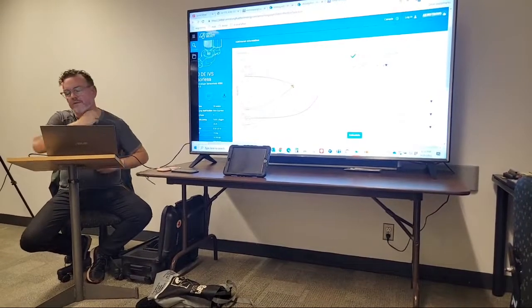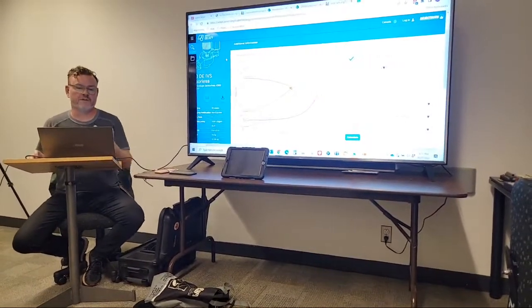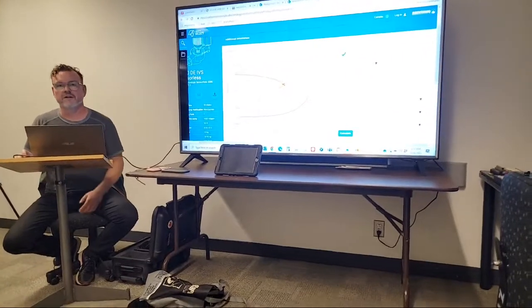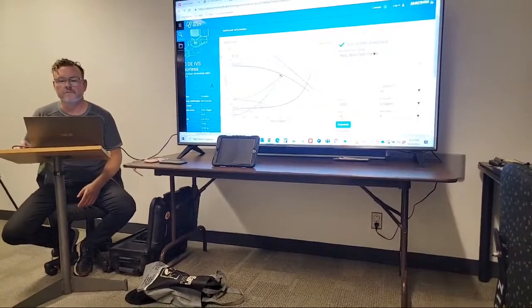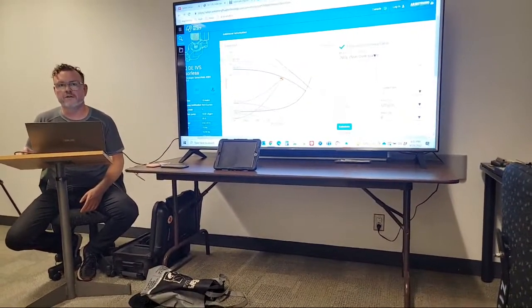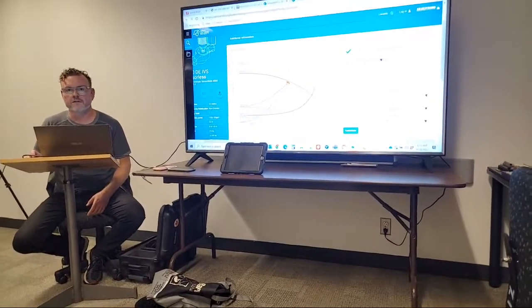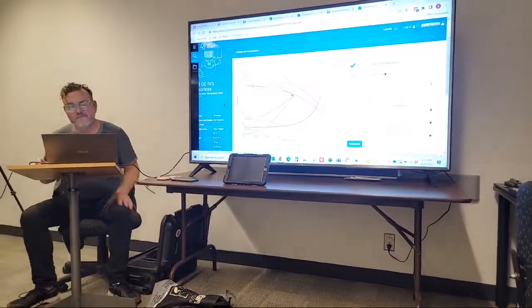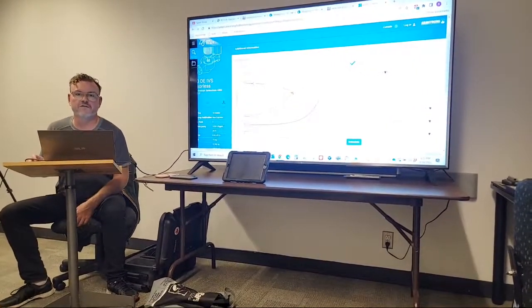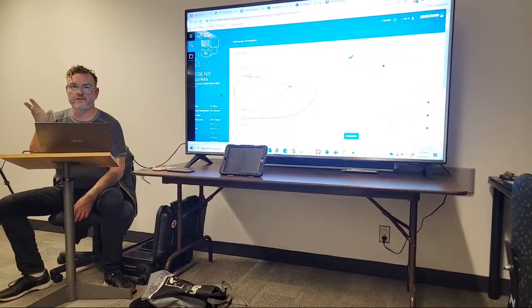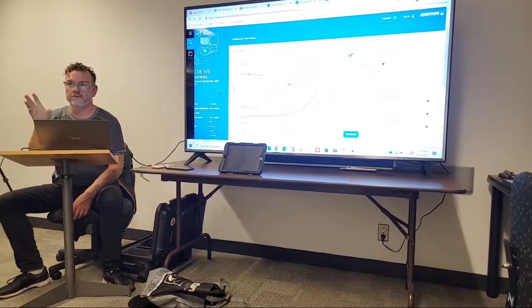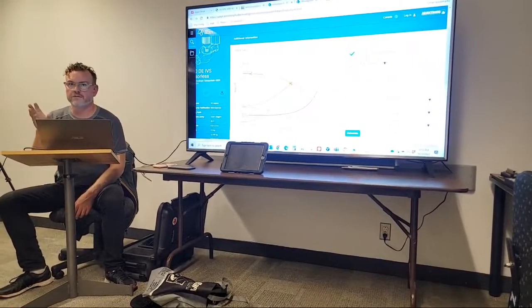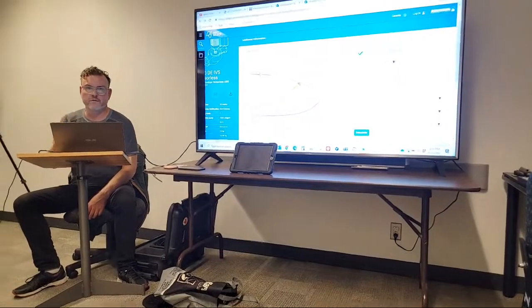I would have to read up on it. Approximately, like if it's a squirrel cage motor, there might be a slight little bit of slip, so the RPM might be a little less than the hertz, just slightly less. But it'll be close. So for the pump affinity laws, when you're trying to calculate stuff, like if you're looking at a VFD and you see the hertz up on the drive or on the wall, you can kind of start to say, okay, you can get the RPM.